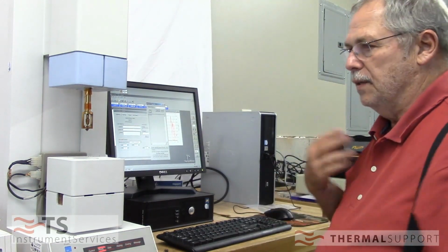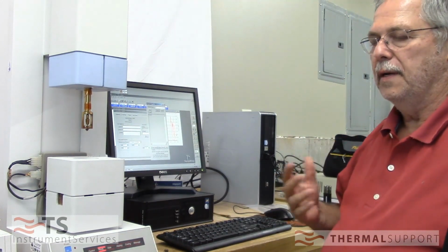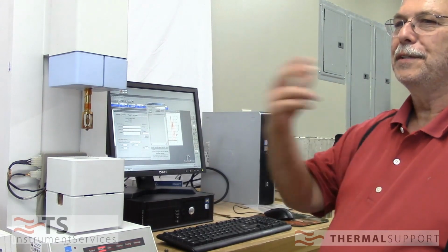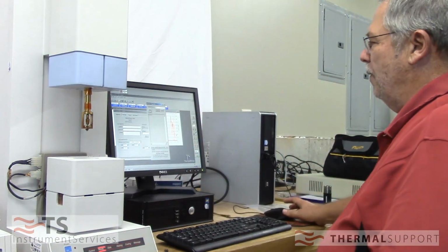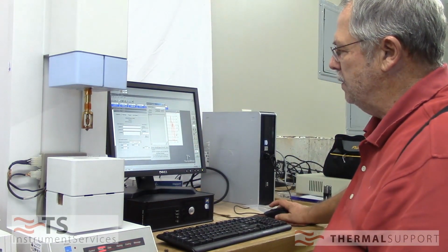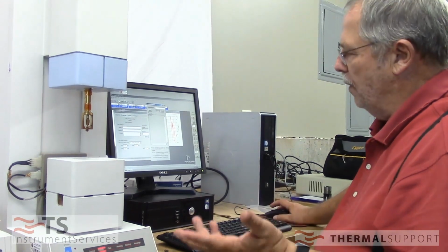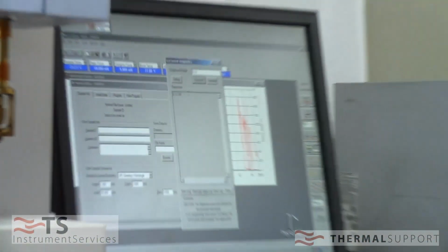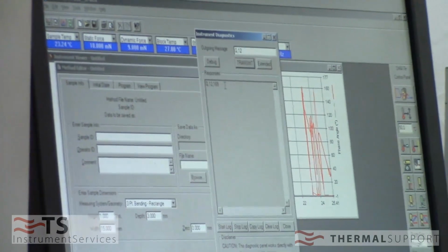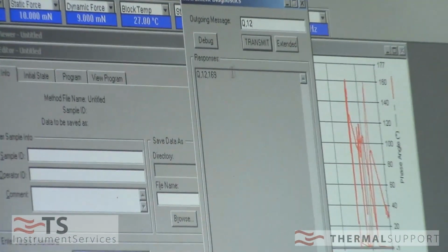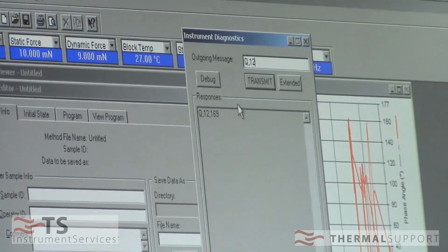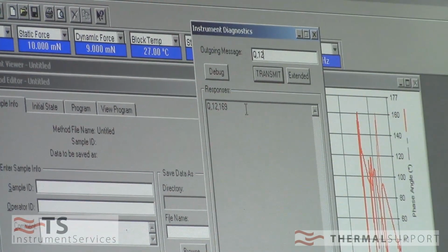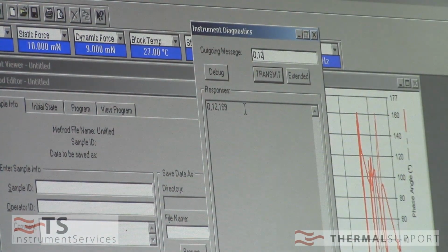And just for our side, to make sure that you're going to be getting what we expect you to on your side, what we've done is we've called up a friction test here, and we're shooting for 150 to 300, which basically should be 1.5 millinewtons to 3 millinewtons. And we've run that test. We've actually run it 3 times, and if you can see here, zooming in, it's coming out with 169 3 times in a row, which is very good.